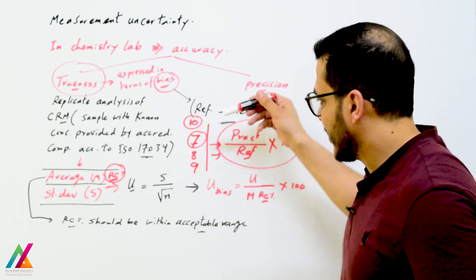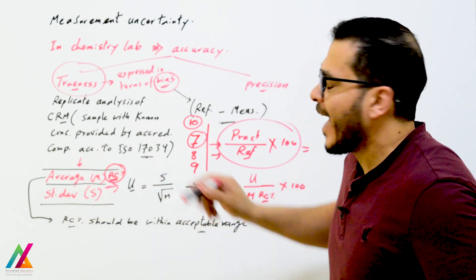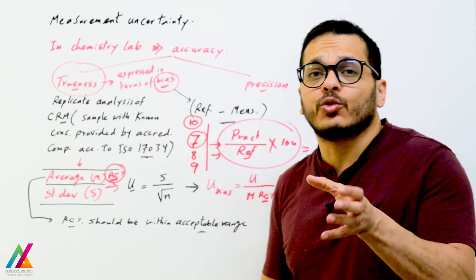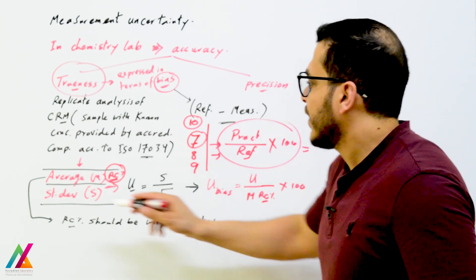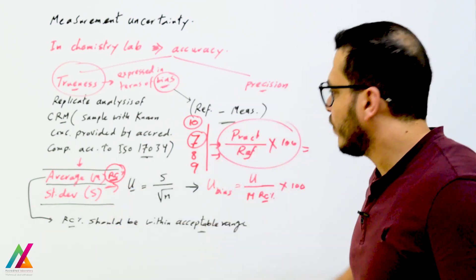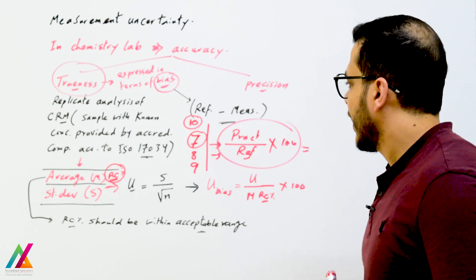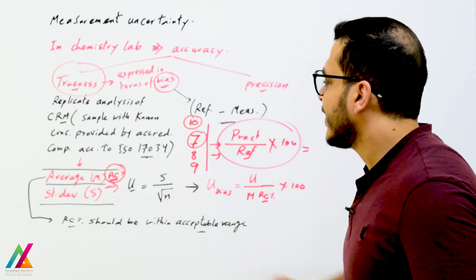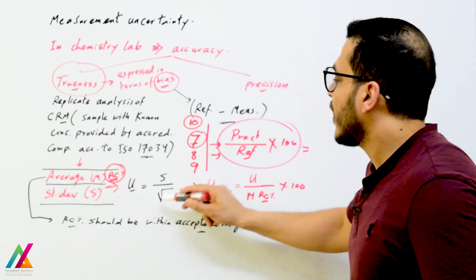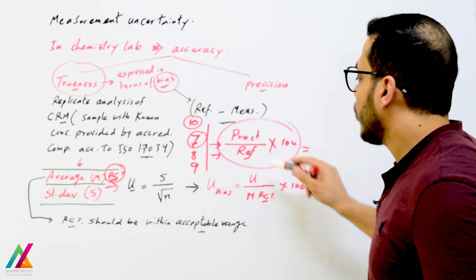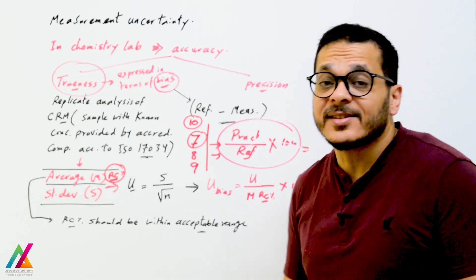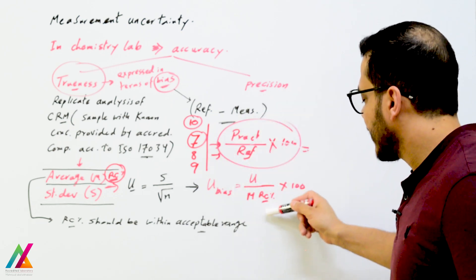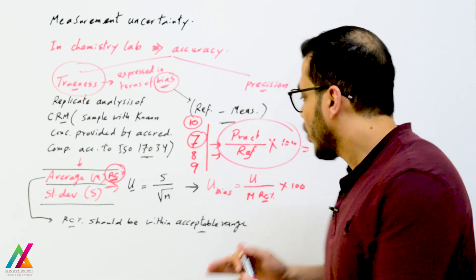From the 6 to 10 results, you calculate the average of recoveries, which must also be within the acceptable range. You then calculate the standard deviation across all results, and from this the standard uncertainty: standard uncertainty equals standard deviation divided by the square root of n (number of replicates). Finally, uncertainty due to bias equals standard uncertainty divided by the average of recoveries, multiplied by 100.